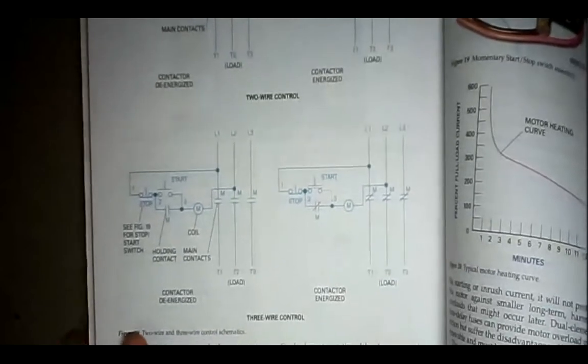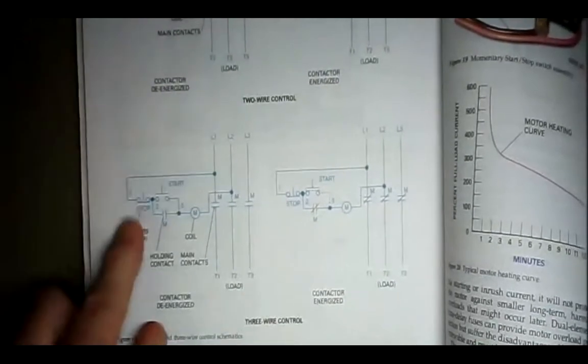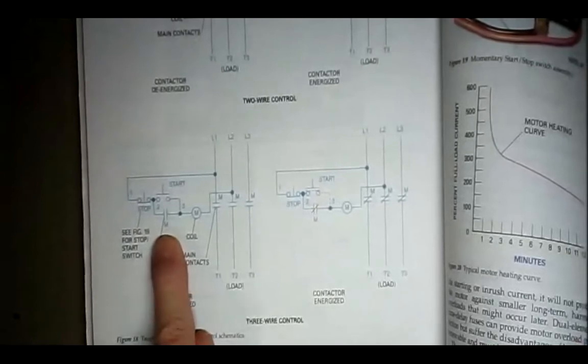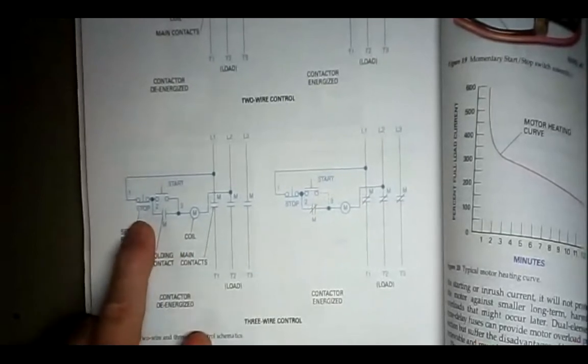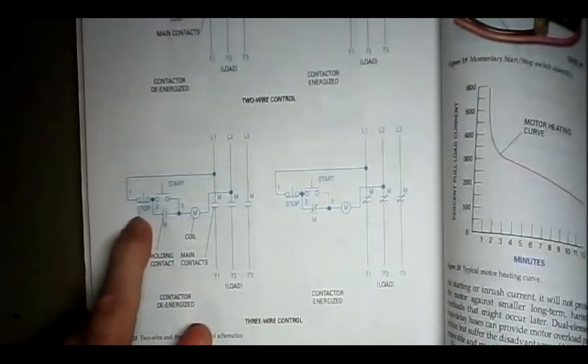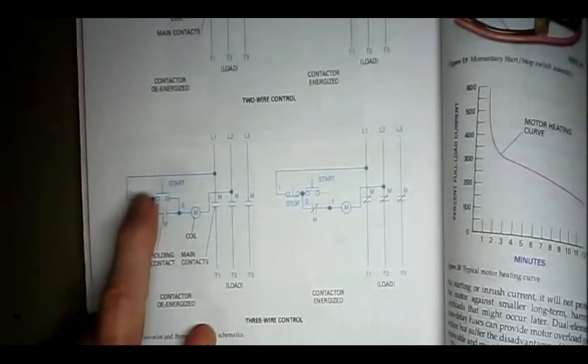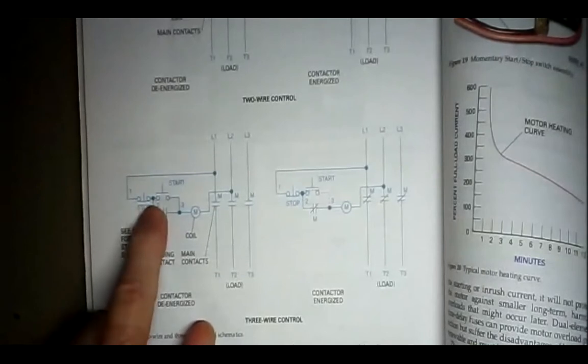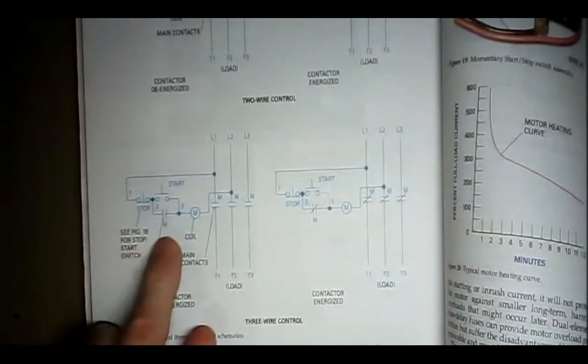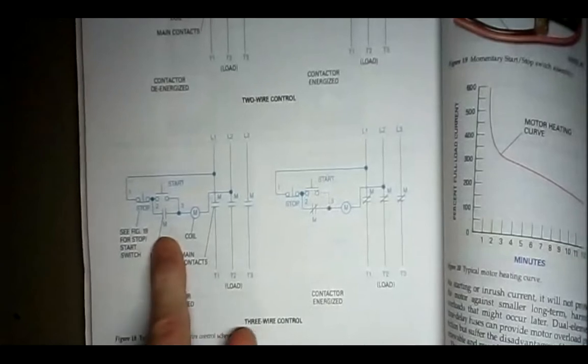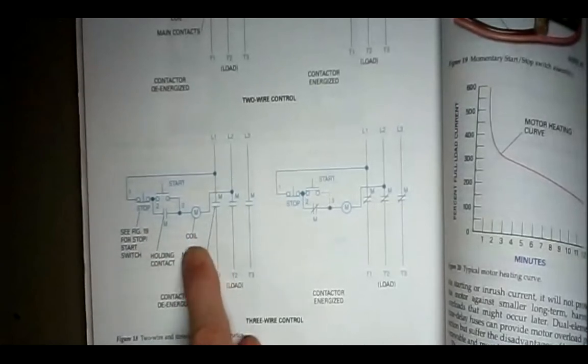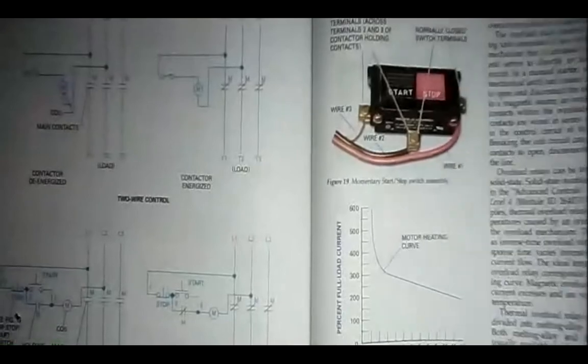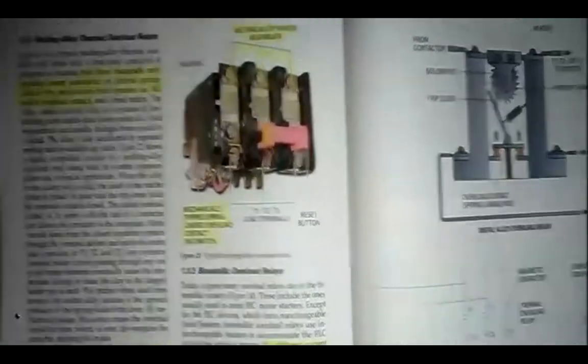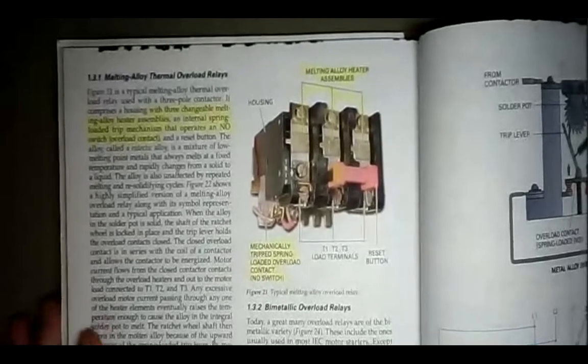Here down below that, they're showing, instead of a single pole switch, a start-stop station where we have a stop button. It's a normally closed, momentary push button, and a start button is a normally open momentary push button. And here's your holding contact, the M contact. It comes off that M motor starter. Okay. All right, I've got nothing over on page 17. Motor heating, page 18. We have quite a few highlights here on page 18.